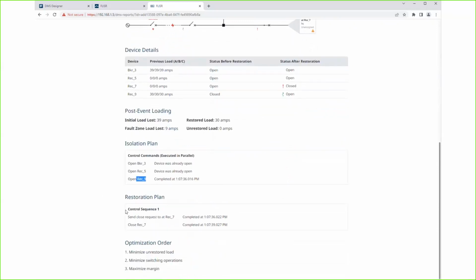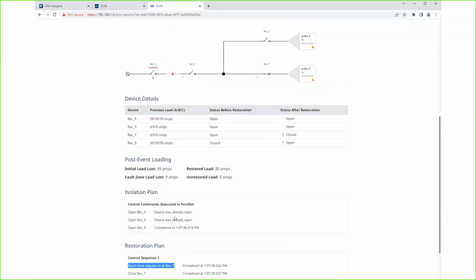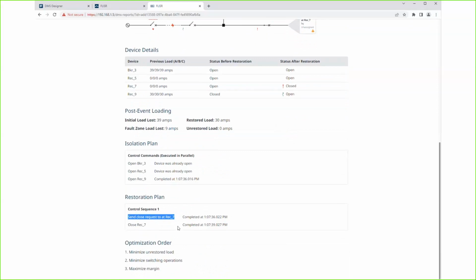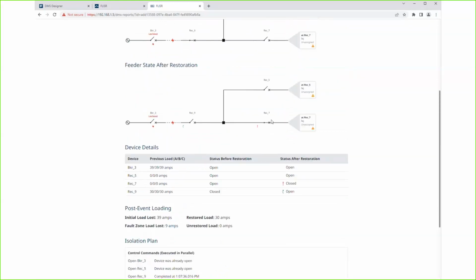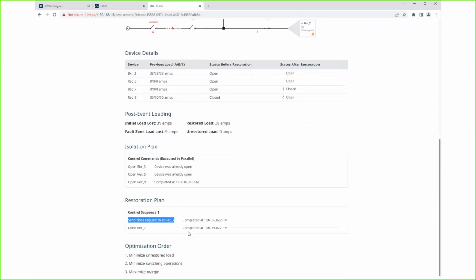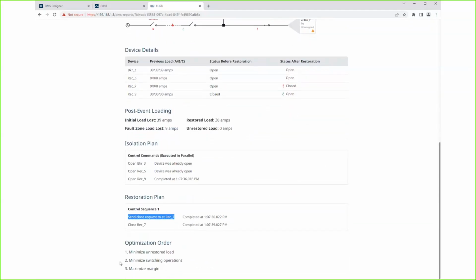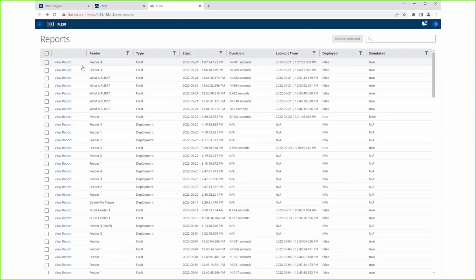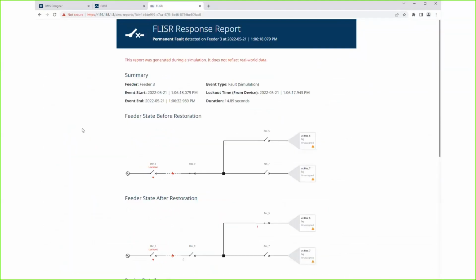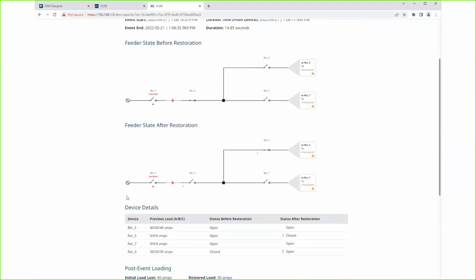What did it do to restore? It talked to the neighbor across that Rec_7 connection, ensured that there was enough margin, and agreed to close recloser 7. And that's the next step, closing recloser 7 completed at 107. It will tell you optimization order, which for now is fixed. We have some interesting ideas about more options to adjust that in the future, but for now, you're picking the one that restores the most load and switches the least amount of things. So here's the other one that we ran, which was that capacity limit situation.